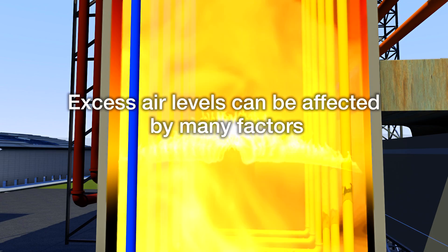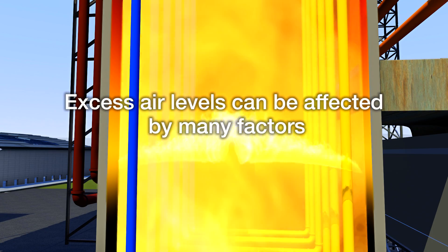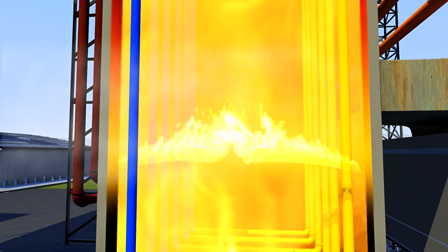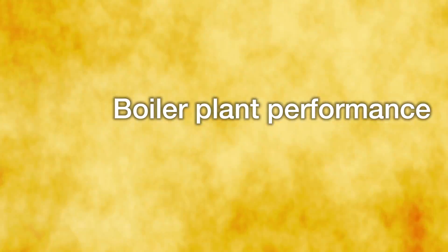However, maintaining the correct level of excess air for combustion can be complicated by variations in the fuel and air, factors including atmospheric pressure and humidity, changes in the heating value of the fuel, and the performance of the boiler plant itself.